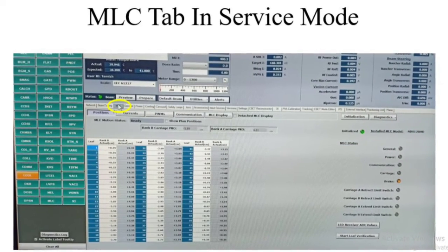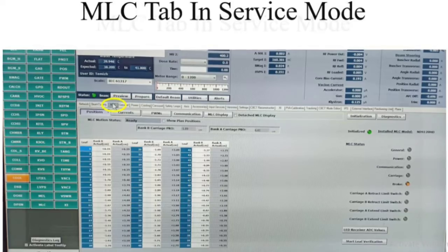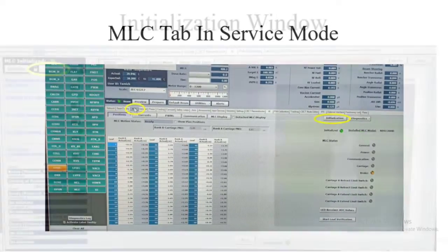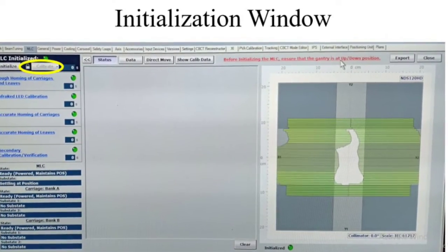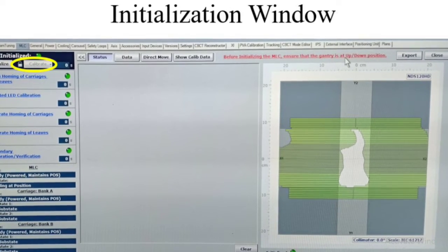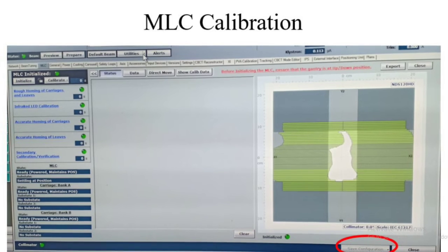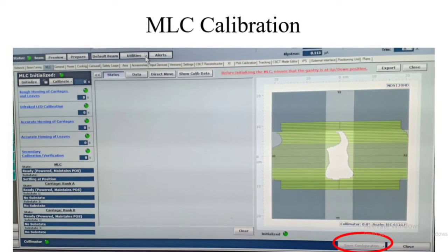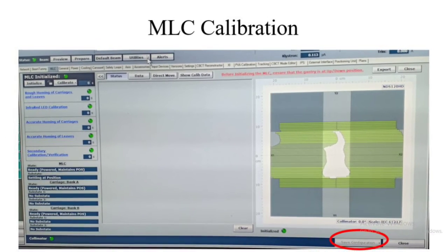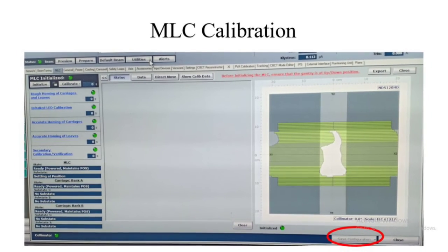So you have to go to the service mode, then open the MLC tab and click initialization. In the initialization window, the calibration option will be locked. So you have to first unlock it and then start the calibration. Once the calibration is over, you have to do save configuration so that the collimator node is updated with the primary and secondary sensor new counts or values. After this, perform the MLC auto cycle to do the MLC mechanical versus optical check.